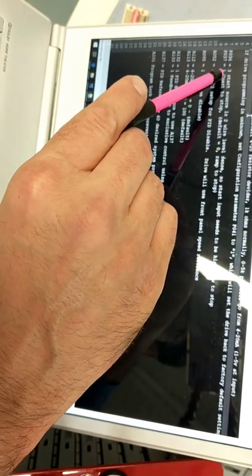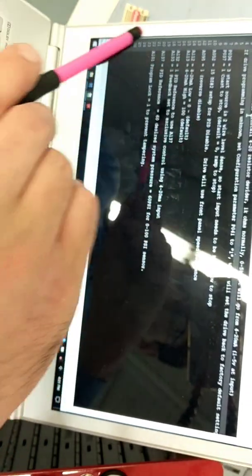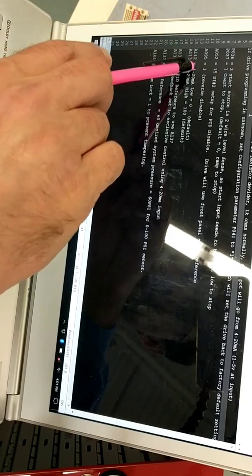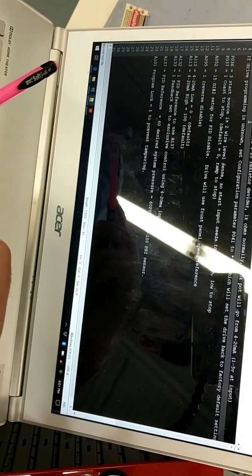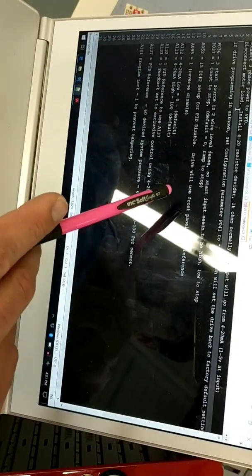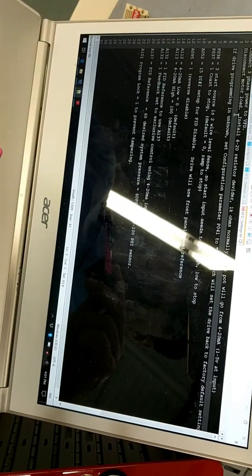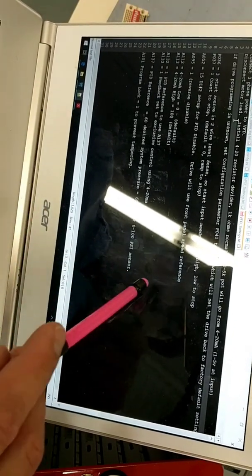P036 is normally, and basically all of these are changed from the default, with the exception of these two. Those got changed back to the default. So P036 means the drive motor is going to start when the start signal is high, and it's set up for a regular switch, not a momentary contact. When the signal goes low, it's going to stop.